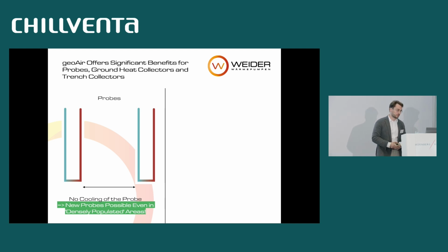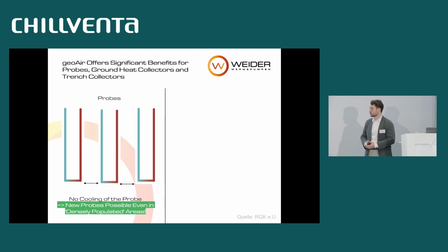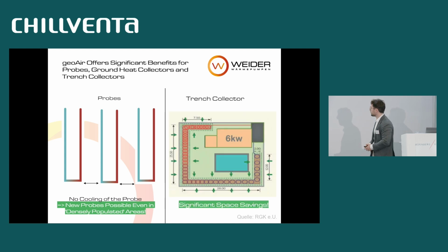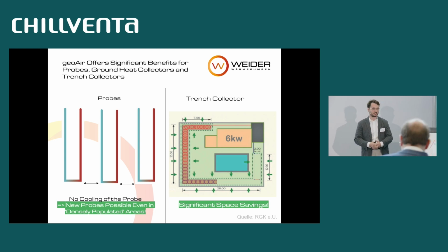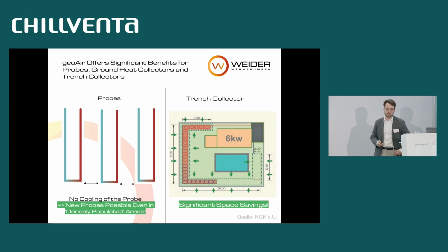Not only does it offer cost reduction for the construction cost of the source, but also since we can fully regenerate the probes or any other source, it is also possible to construct probes in densely populated areas where cooling of the probes is no problem. So we can place probes in between probes where it might not actually be allowed to do so. And also, if you talk about trench collectors or surface collectors, we can significantly reduce the space. As you might know, in densely populated areas, the use of space is very important, and this is also possible since we can regenerate the source during winter.